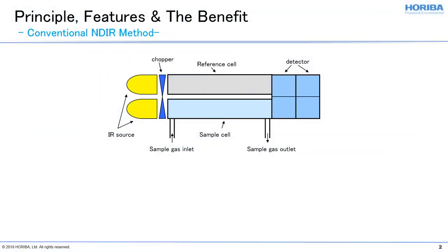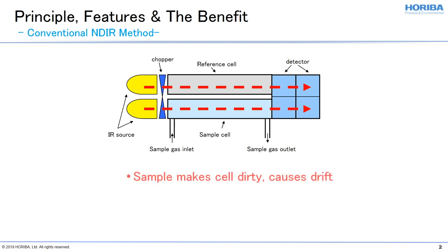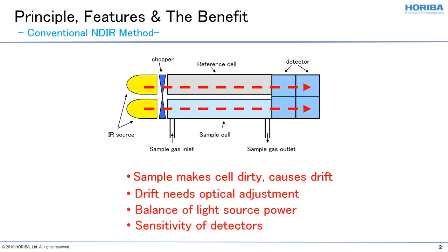This is a conventional NDIR method. Basically, it has two light sources, a sample cell and a reference cell with two detectors. The two detectors read differences of absorption of light between the reference cell and sample cell. The weak point for this method is that dirty sample gas is continuously introduced into the sample cell, causing drift and requiring optical adjustment. Also, the balance of light source power and sensitivity of the detectors is crucial for accurate measurement.